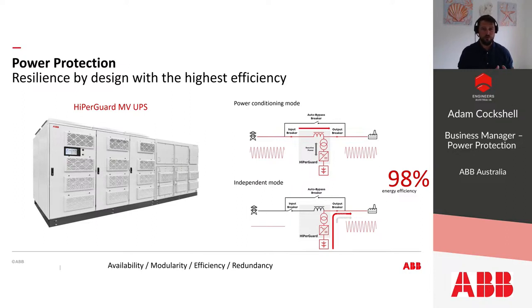The transition from low voltage to medium voltage level is a natural progression for power protection for large critical power facilities. Among the most significant benefits is the reduced cost to the critical power facility build and operation. Larger protected load banks, lower switchgear count, reduced size of busways and cabling with lower losses.